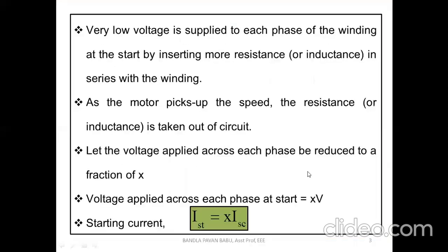Right. Next, the starting current. I_ST equal to, let us consider, X into I_SC, that is the short circuit current. As we have gone through the working principle of how the motor functions, we came to know that because of the lower resistance, at the starting of the machine, when high inertial loads are connected, it draws a huge amount of current. How can we term it as a huge current? We are terming it as the short circuit current, in which the maximum current is drawn in the machine.